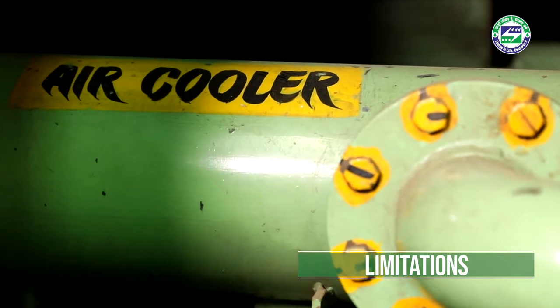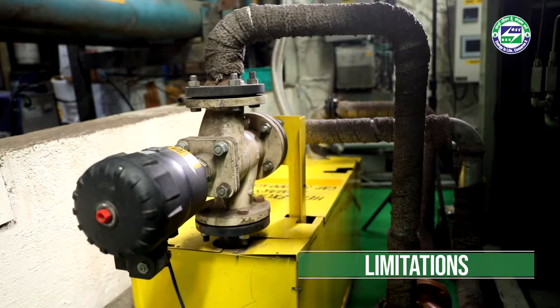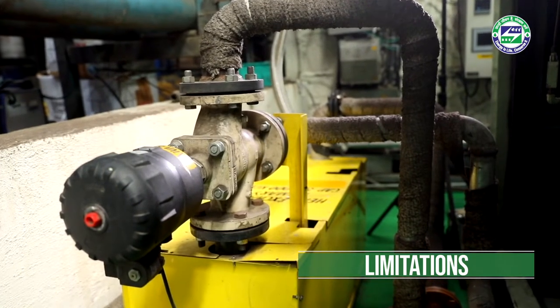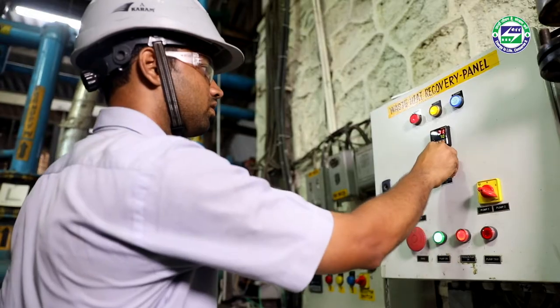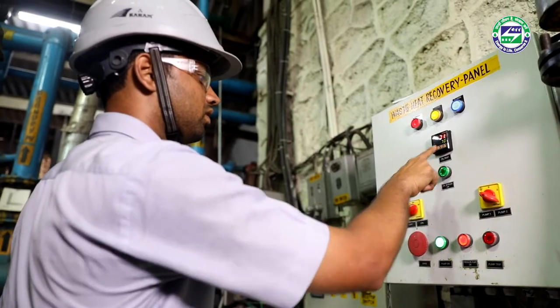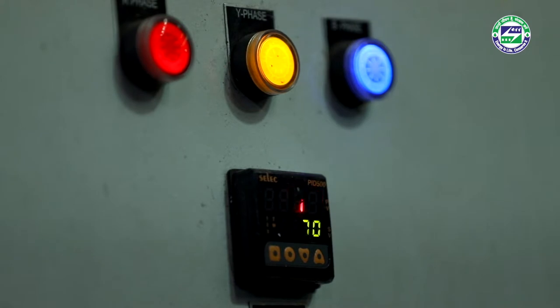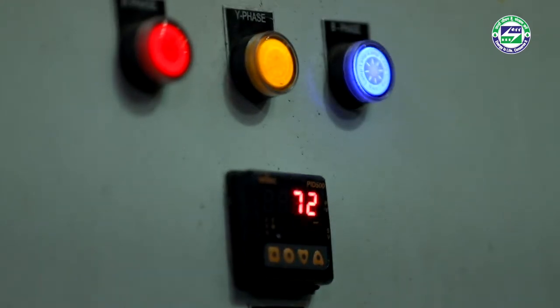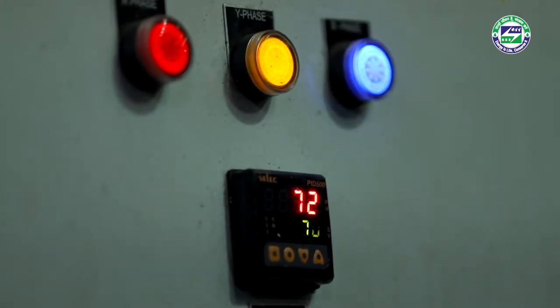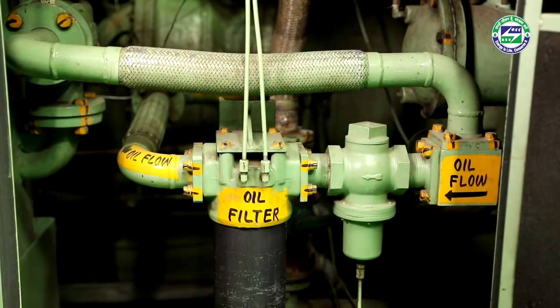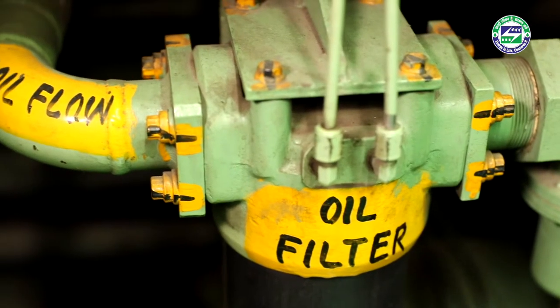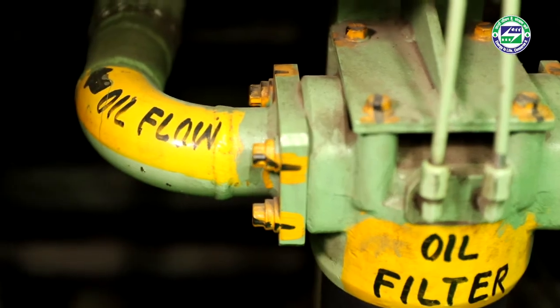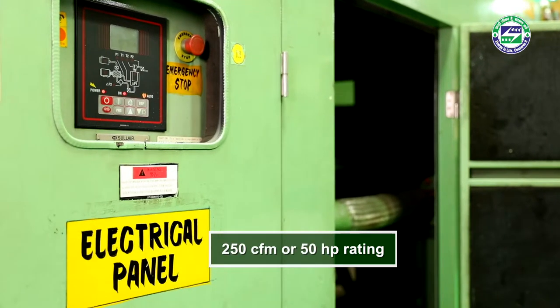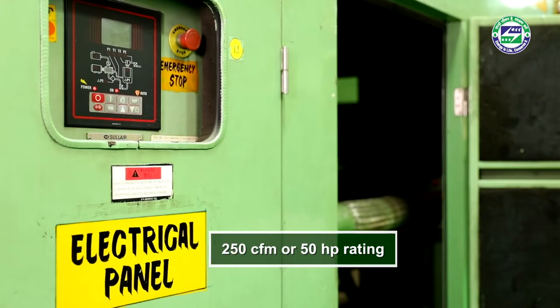Energy recovery from air-cooled compressor installations will not always give heat when it is required, and perhaps not in sufficient quantities. The quantity of recovered energy will vary if the compressor has a variable load. Waste heat recovery from a compressor is economically feasible for compressors above 250 CFM or 50 HP rating.